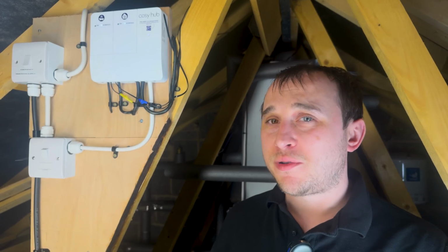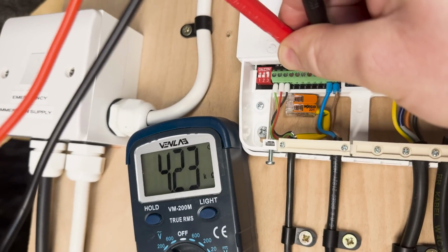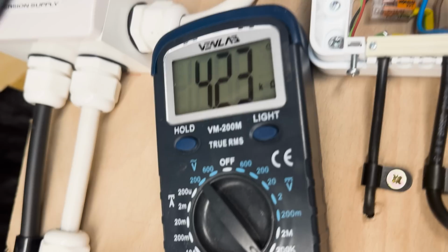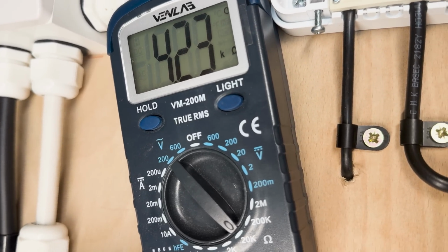But he gave me some tips on how to find out what temperature probe it was. One of them was using a multimeter, and he told me the multimeter would tell me if it's a 10K, 20K or 30K probe. Now, it didn't give the exact readings that he said it would on the resistance. The resistance didn't make sense. That's because you have to test it at 22 Celsius exactly.